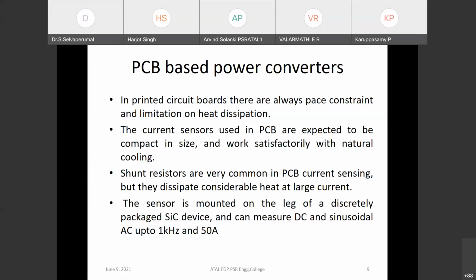integrated circuit based sensors and magnetoresistive sensors have inherent galvanic isolation and are usually employed where high bandwidth and DC or AC measurement capabilities are required. So these sensors are available commercially with a current measuring range up to 100 ampere and consume minimal power even at large currents, right? So linear integrated circuit based current sensors have a typical bandwidth of 100 kilohertz, while magnetoresistive sensors' bandwidth is relatively high, up to 2 megahertz.